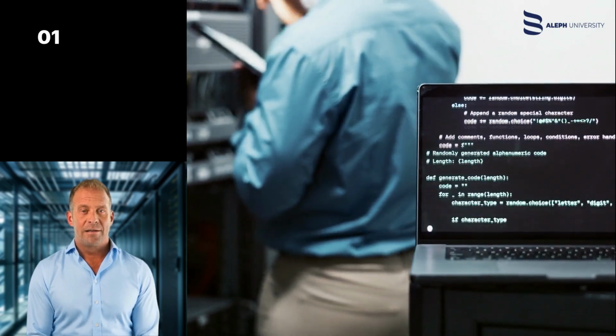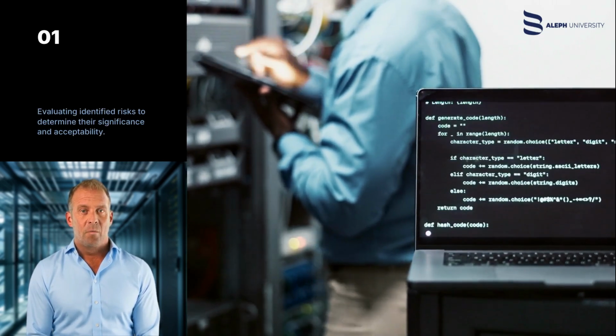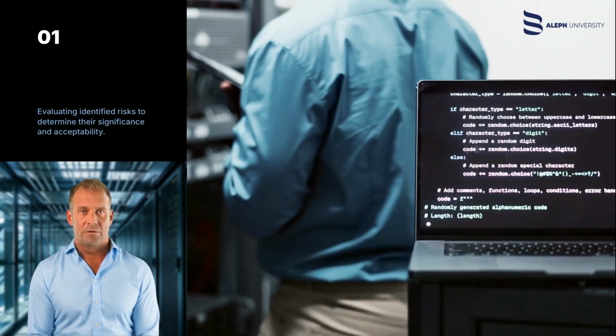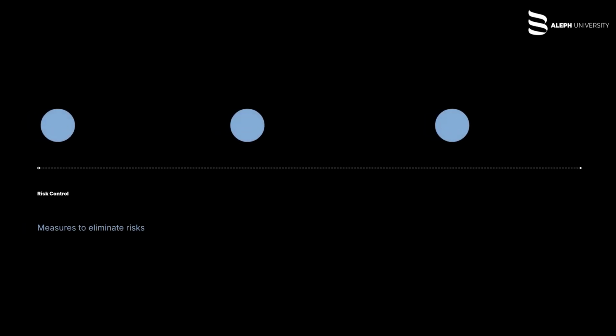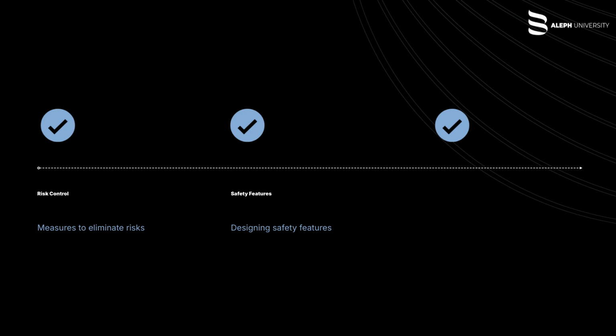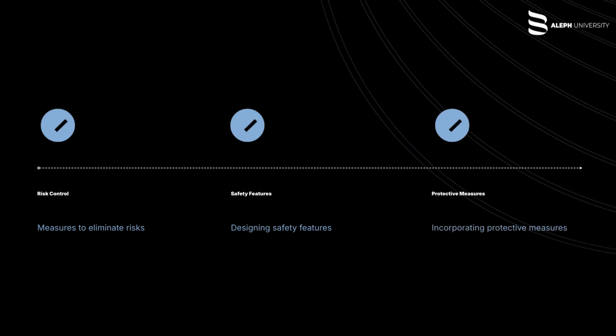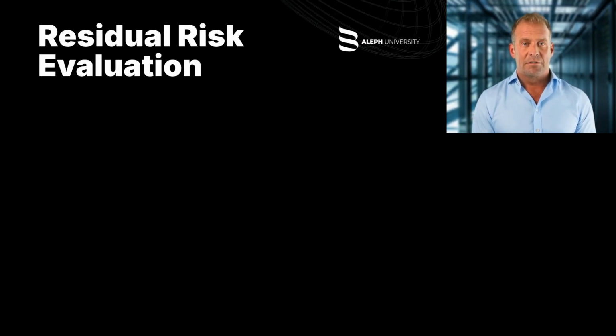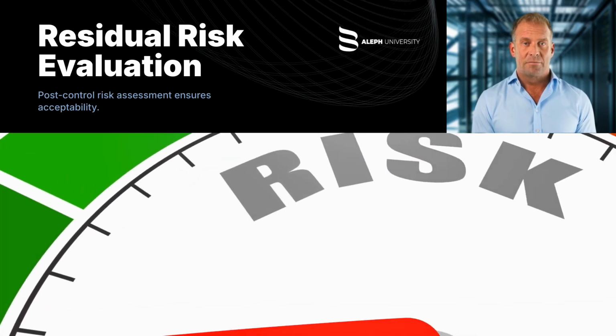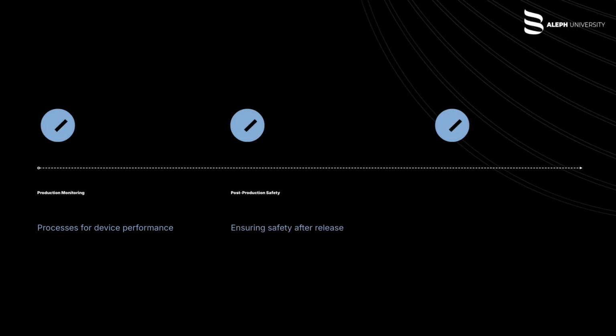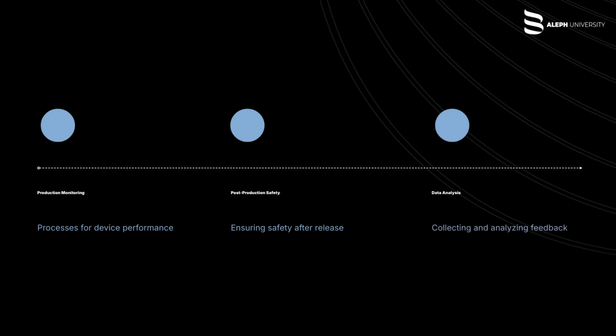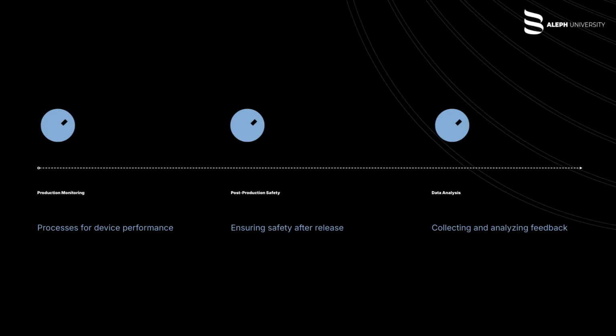Risk evaluation, assessing the identified risks to determine their significance and whether they are acceptable based on predefined criteria. Risk control, implementing measures to eliminate or reduce unacceptable risks to acceptable levels. This includes designing safety features, incorporating protective measures, and providing information for safe use. Residual risk evaluation, after implementing risk control measures, evaluating any remaining risks to ensure they are acceptable. Production and post-production monitoring, establishing processes to monitor the device's performance and safety during manufacturing and after it has been released to the market. This includes collecting and analyzing data on device performance, user feedback, and any incidents reported.